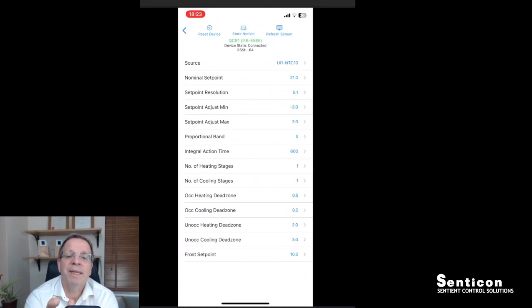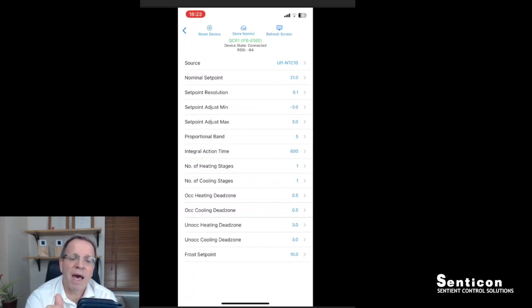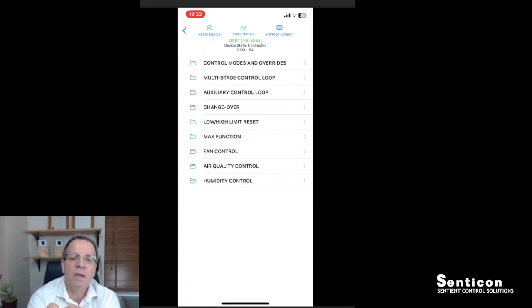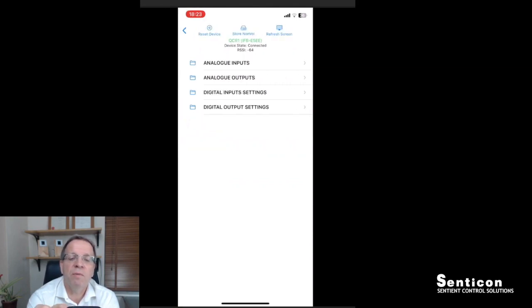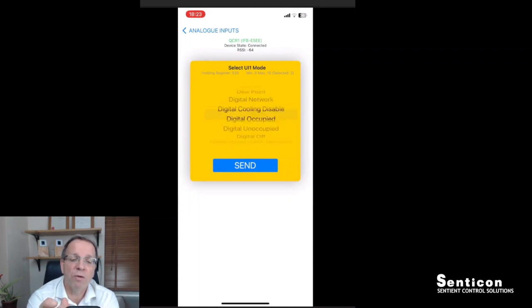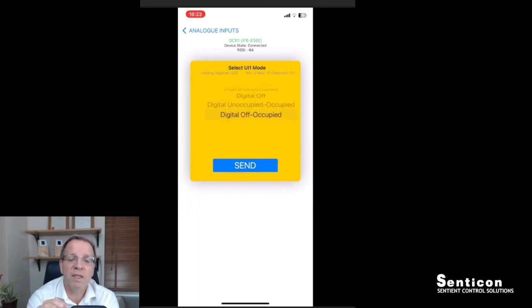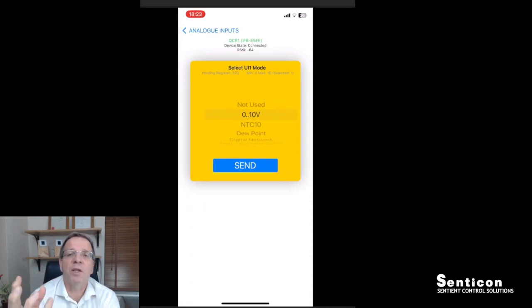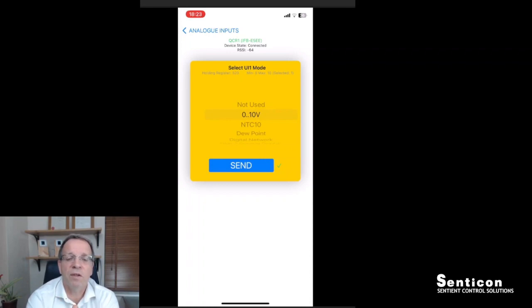The main menu is the multi-stage control loop, where you can have up to six-stage temperature control. In this case we have set up the control source to NTC 10 on Universal Input 1, and then we can change the nominal set points, proportional bands, dead zones, and so on — which are typically used in a control scheme for heating and cooling. Going back to the input/output settings, on analog inputs I can easily select from the universal input mode how that input is configured — whether it's a digital on/off, NTC 10, 0–10V, or maybe an external CO2 sensor. You click send and the configuration is applied — it's as simple as that.